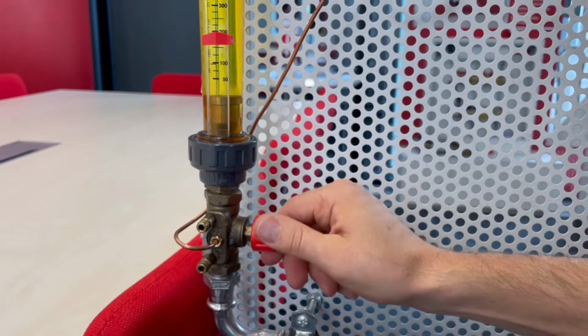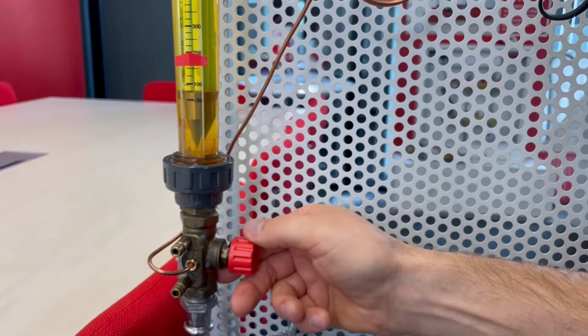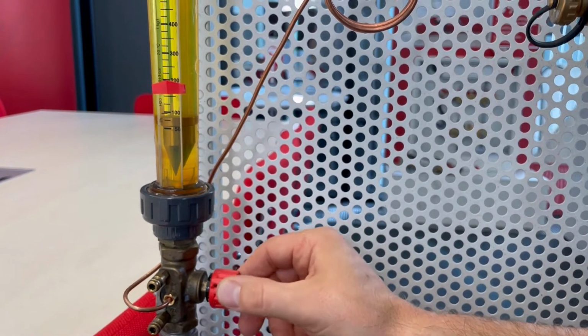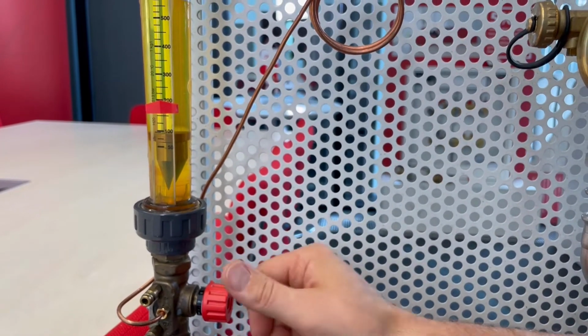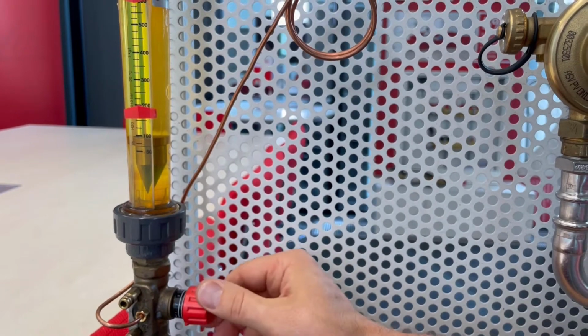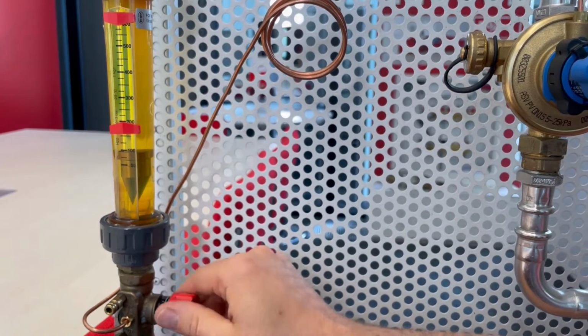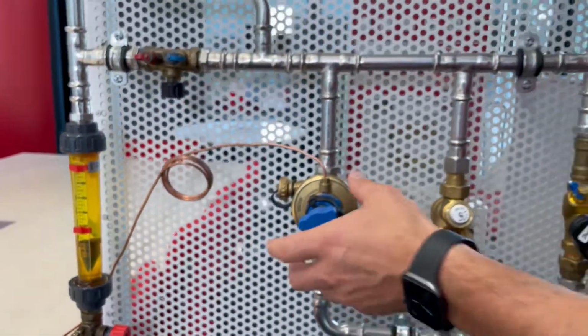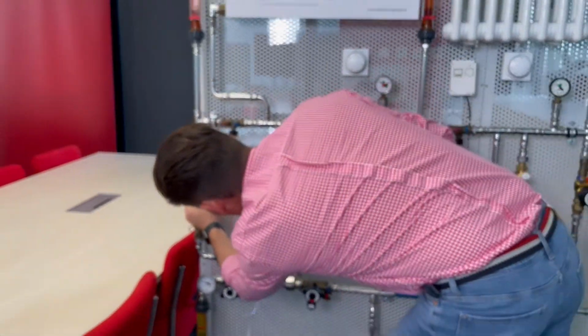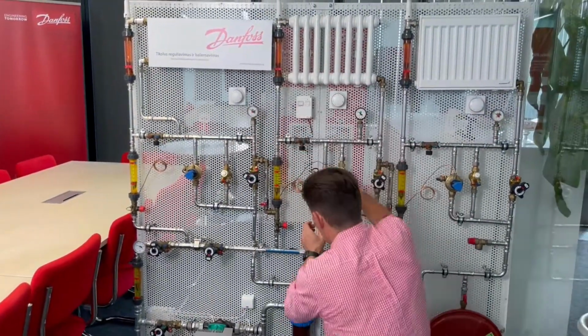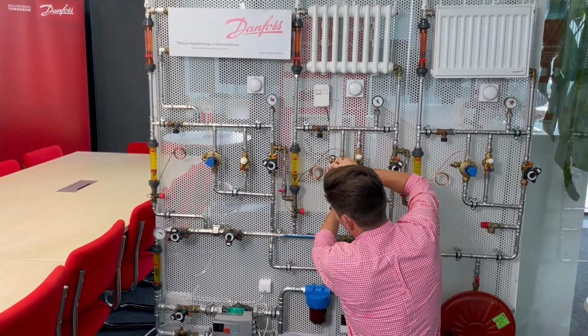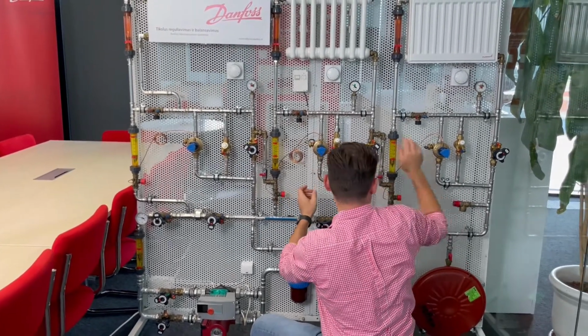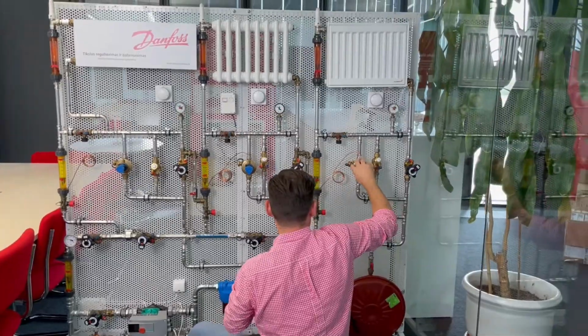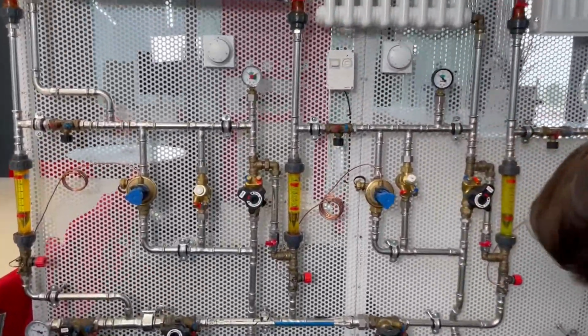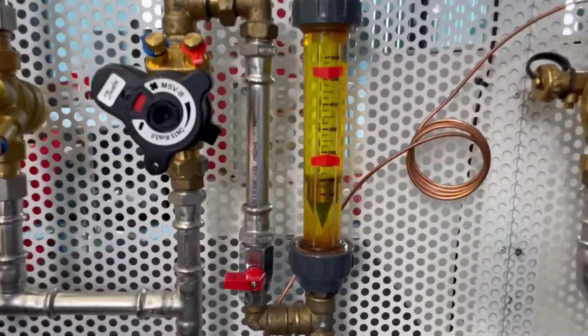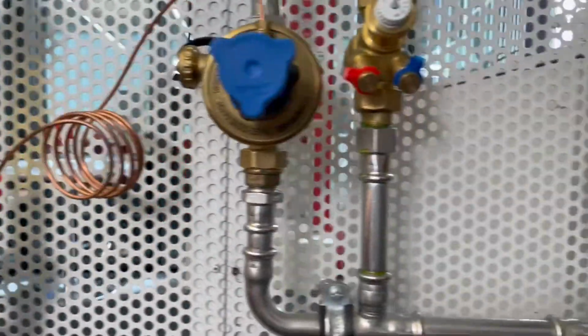Also, I can regulate here with the manual balancing valve, but it is better not to squeeze this balancing valve too much, because it takes authority on itself, and then we lose authority for the thermostatic radiator valve, which in a simple way means we lose accuracy of regulation of temperature for the radiator thermostat. So I set 100 liters here. I set 100 liters here. Okay, and let's set 100 liters here. Okay, so we have everywhere 100 liters, 100, 100, 100.